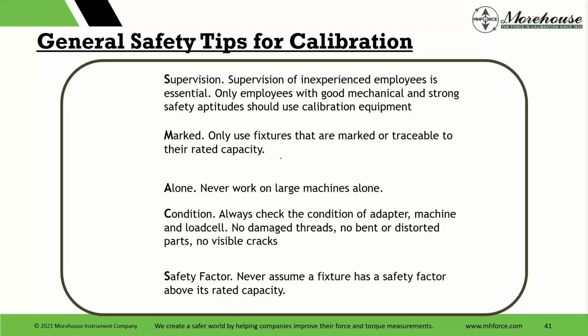This should be everybody's habit. Always check the condition of the adapter, machine, and load cell. No damaged threads, no bent or distorted parts, no visible cracks. That's visual. It's the easiest thing somebody can do. If there are damaged threads, if there are visual cracks, replace it. Not even worth doing much of anything other than replace, because you're likely going to spend too much money on all the testing that's required, and it's just cheaper to buy a new one. And then safety factor. Never assume a fixture has a safety factor above its rated capacity. Being a manufacturer and dealing with several manufacturers, I cannot state this enough. Everybody seems to treat things differently. For us, a max capacity is a 2-to-1. Somebody else could have it at 1.6-to-1, somebody could have it at 1.2, somebody could have it at 4-to-1. It's all over the place.